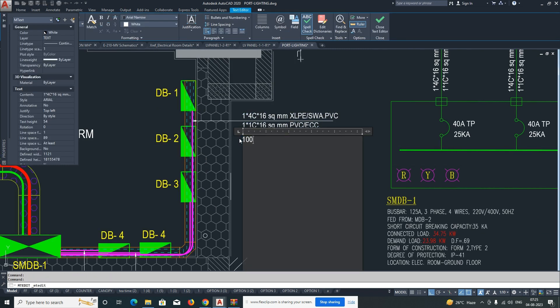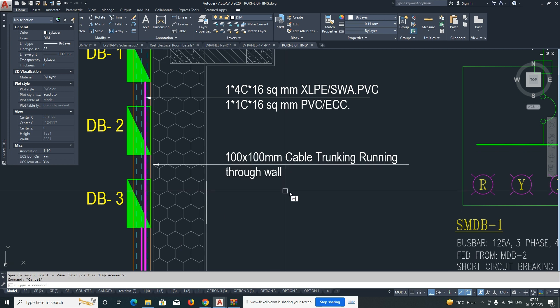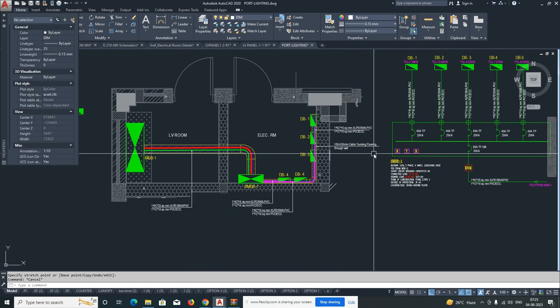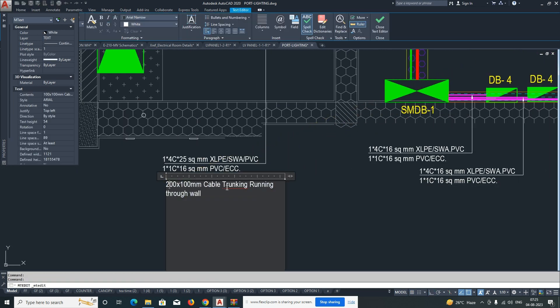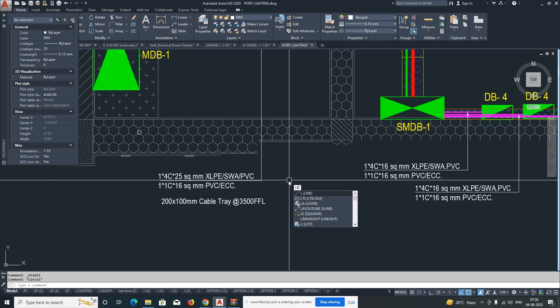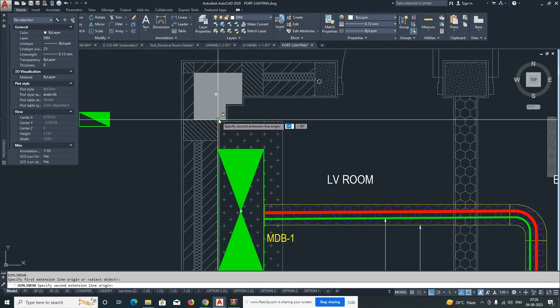This is 100 x 100mm cable trunking running through the wall. Like that you can give tags for all the cable trunking. For the cable tray you can also give a tag — for example, 200 x 200mm cable tray at level 3500mm, as per the room height. You can give separate names for the cable trays and add dimensions as per the schedule.